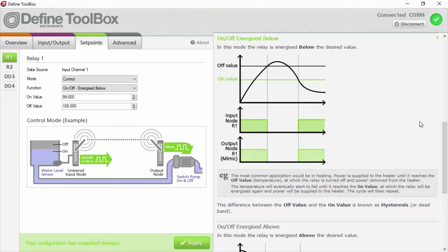And you'll notice that on the right hand side here, our help is showing us a nice graph of the behavior here. So I can set up points here, and that's going to show us how it's going to work. So let's say we want the pump to turn on when there's 6 feet of water, and we want it to turn off when there is 14 feet of water in the tank. I can now click apply.